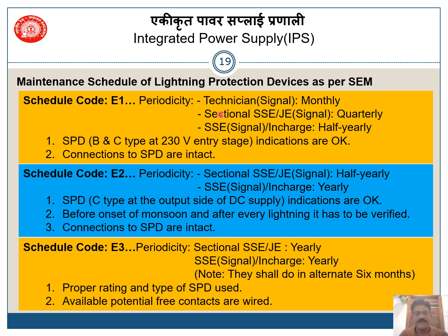As per the Signal Engineering Manual, what is the periodicity schedule of maintenance of lightning protection devices as per SEM? The periodicity: for a technician, signals shall be monthly, SSE/JE shall be quarterly, while SSE in charge shall do all the required checks once in half yearly. What are the checks that have to be done? SPD, B and C type at 230 volts entry level, indications are okay or not. Any failure indication shall be replaced with a new SPD. All the connections to the SPD are intact.